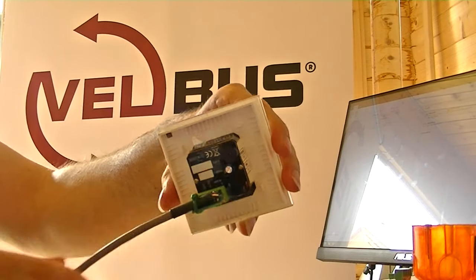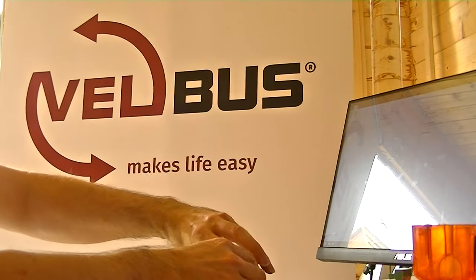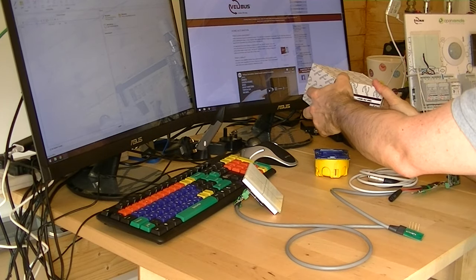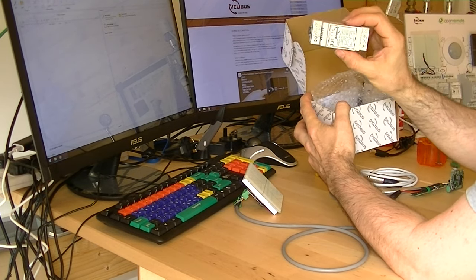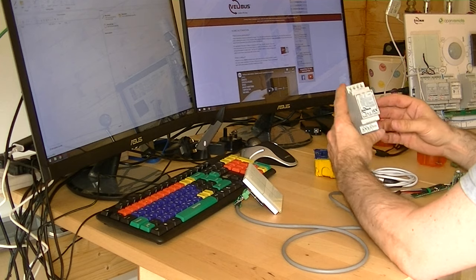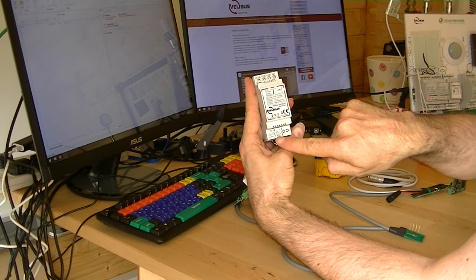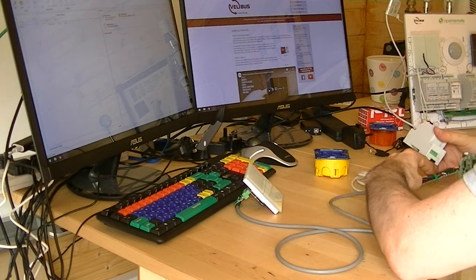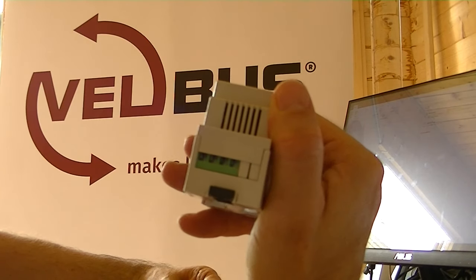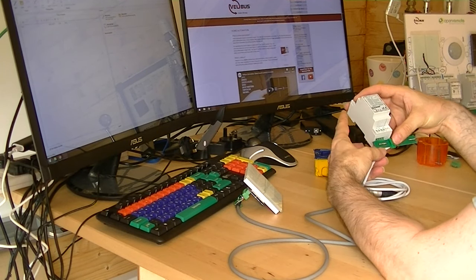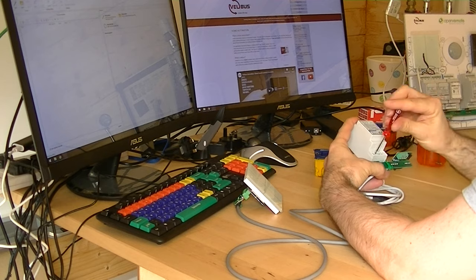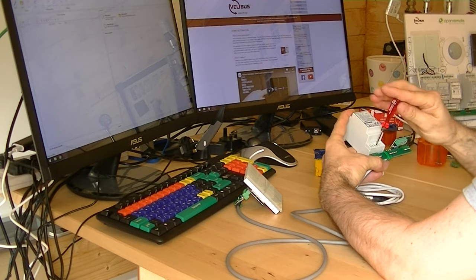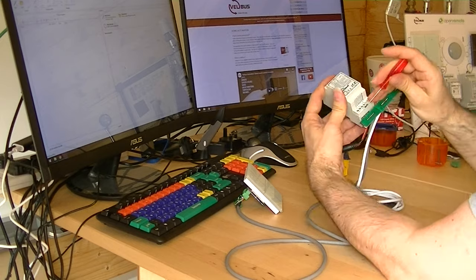So when you're commissioning, you just simply plug it in and push it onto the back box. Make sure it's all four lugs have seated nicely. And what we'll do now is we'll hang the single channel relay on there. So let's give a quick look at it. At the bottom is the four Velbus connections, the data and the power. And at the top we've got our connections to the outside world. So in this case it's a single channel changeover relay. So there's your four rising cages. I'd strongly advise unwinding those so there's plenty of space there. And then just slide the pins of the PCB up into it. And then do them up. If only I could work at this speed all the time, I'd make a fortune. There you go. That's all four in.